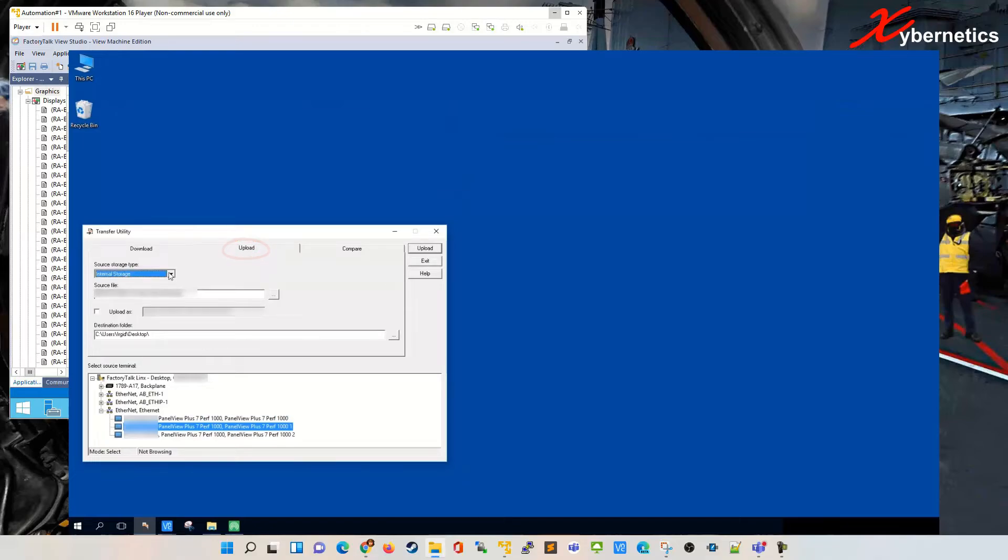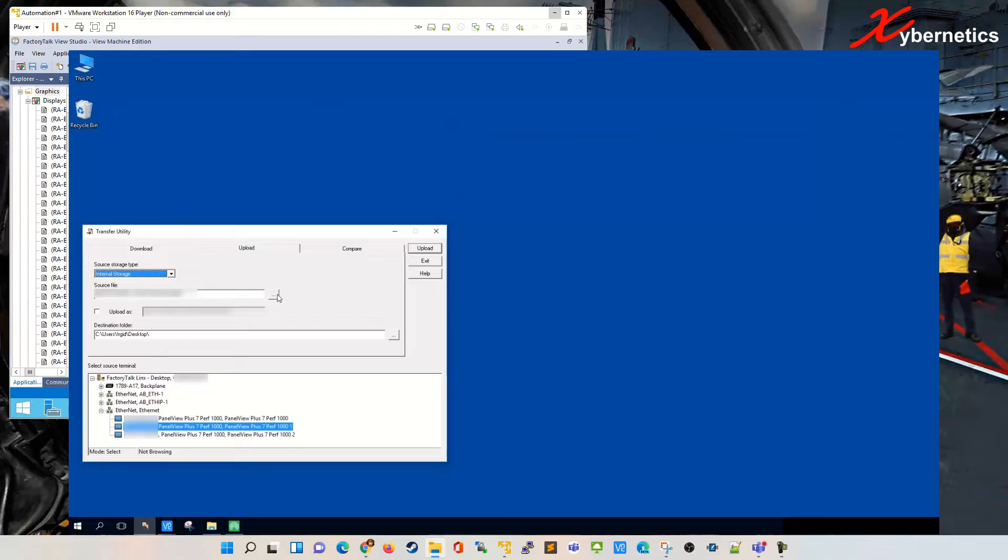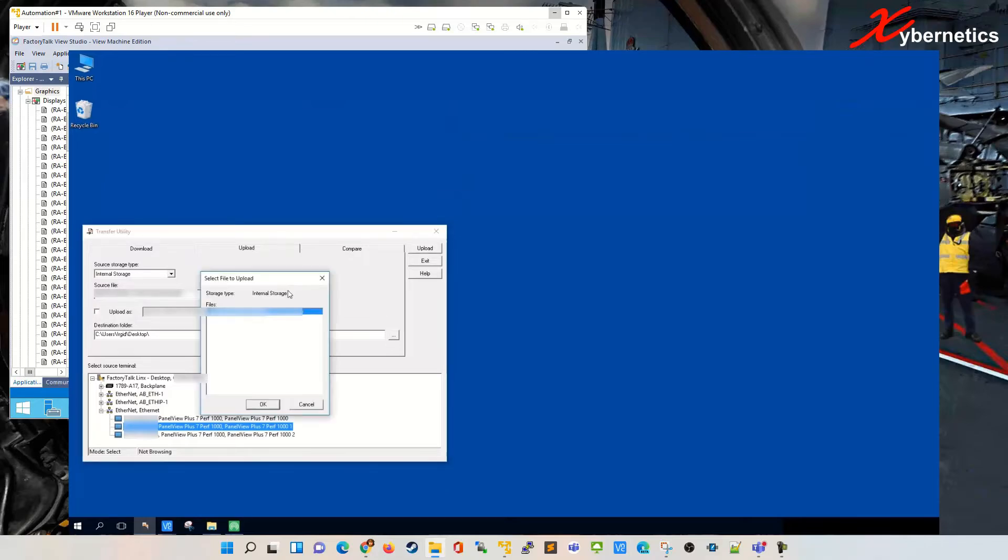Depending on where you have stored your MER file, you select the storage type. Mine is gonna be on internal, and you can click on these three dots here. If you click the three dots and you see the file that you are anticipating from the panel view, you know that your connections are good. This is my file and I know that's the file that's been there.